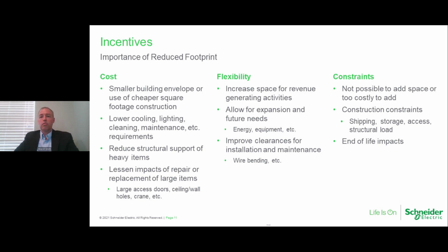The existing electrical room was not sufficient for the modern needs. If we had used metal clad switchgear, they would have had to blow out the wall of the electrical room and taken out one of their $1 million condos. Instead, we were able to fit greater electrical capacity into a smaller footprint and save them that revenue generating space.